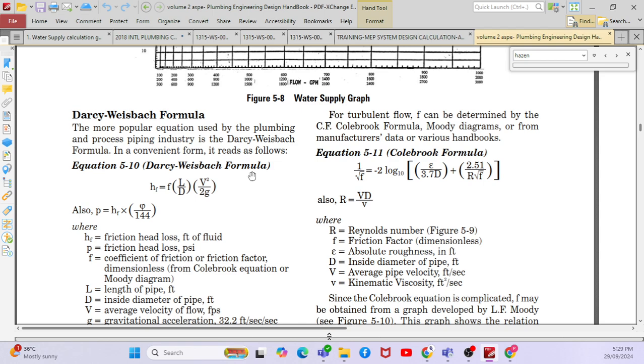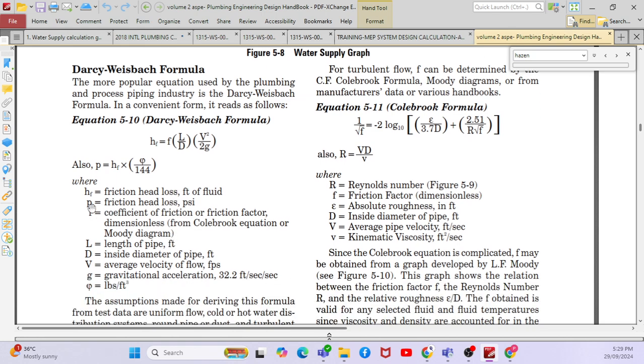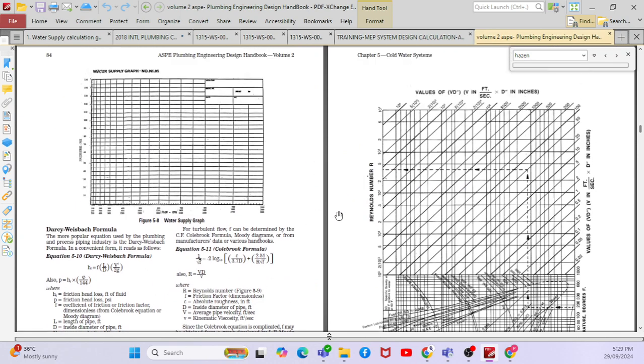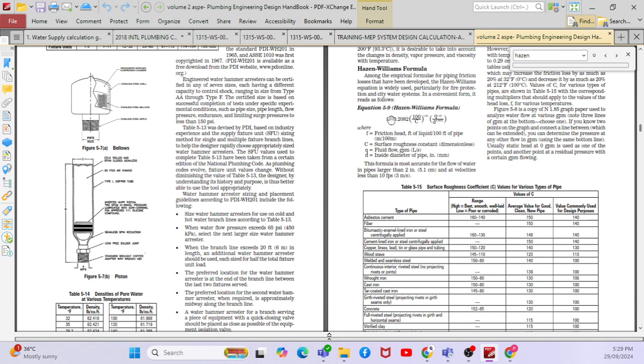Similarly, you can calculate pressure drop using the Darcy-Weisbach formula: HF = F × (L/D) × V²/2G, where HF is friction head loss, P is friction head loss in PSI, F is the coefficient of friction, L is the length of the pipe, and D is the inside diameter. You don't need to do this calculation every time — you can use the IPC standard chart, which gives friction loss per PSI per 100 feet of length.